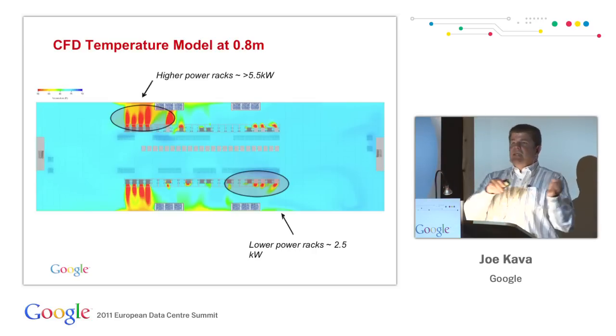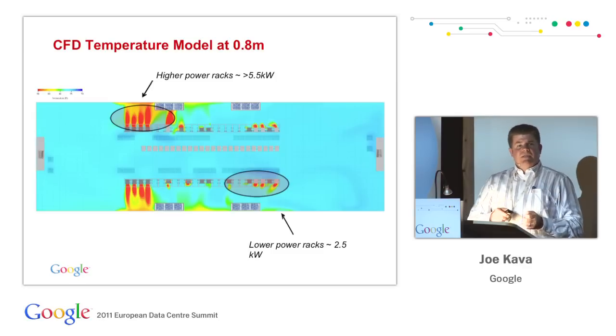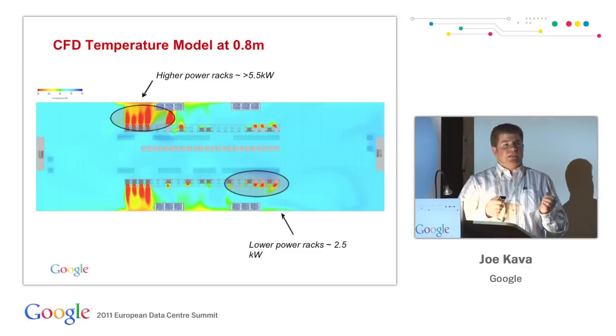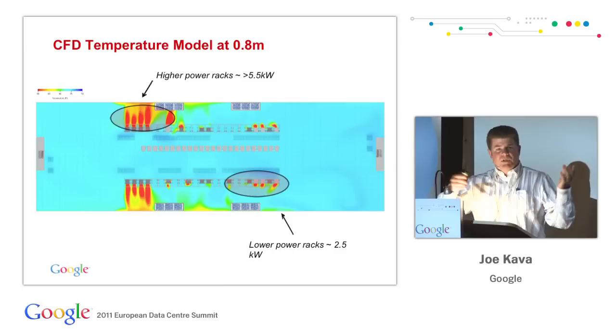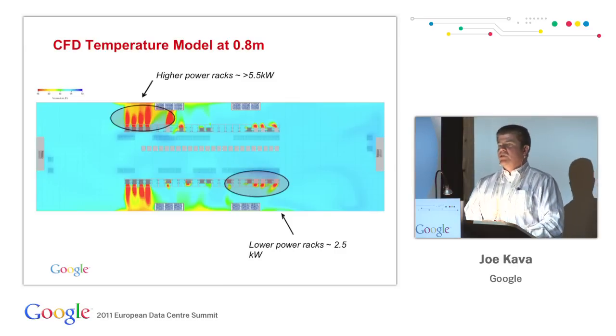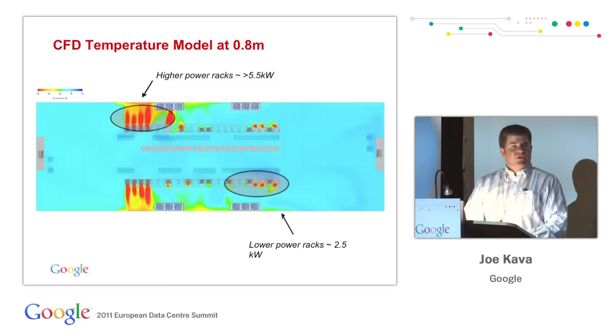And to make it even worse, some of the higher density cabinets were exhausting directly into the return air intake of the CRAC unit, which was, of course, causing that CRAC unit to work harder than it should have. It was seeing an artificially high temperature in the room, and it was turning up all of its compressor stages. So it was really inefficient.